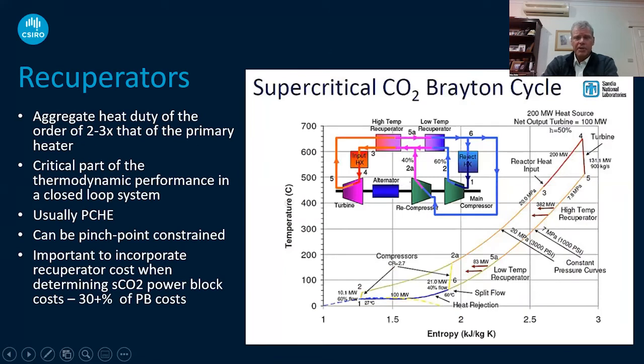Now, just talking about some of the critical components in the supercritical CO2 cycle: this particular curve shows a cycle which has 50% efficiency, 200 megawatts thermal of heat being provided to the cycle, and 100 megawatts net turbine output. You can see that the high temperature recuperator is actually transferring about 380 megawatts of heat, and the low temperature recuperator about 83 megawatts of heat. So there's more than double the amount of heat being transferred through the recuperators than there is in the primary heat exchanger going into the cycle.